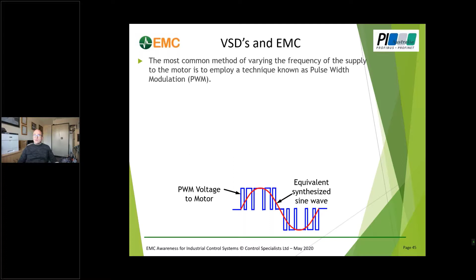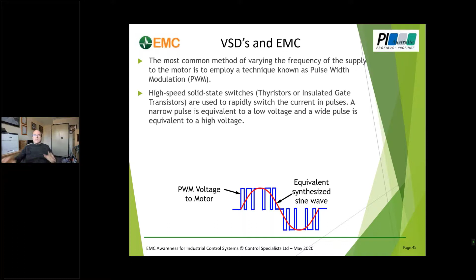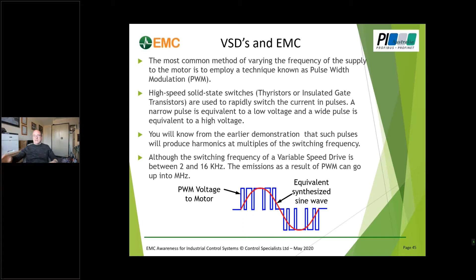So we now know from what we've seen that they're going to generate a wide range of emissions, because that's what we get with square waves. We're using thyristors or IGBTs, insulated gate bipolar transistors, to switch these on or off. As the earlier demonstration should have shown you, the potential issue is that we're switching at an adjustable frequency of between 2 and 16 kilohertz. But that's just the fundamental frequency — the range of emissions goes well beyond 16 kilohertz, up into the megahertz.